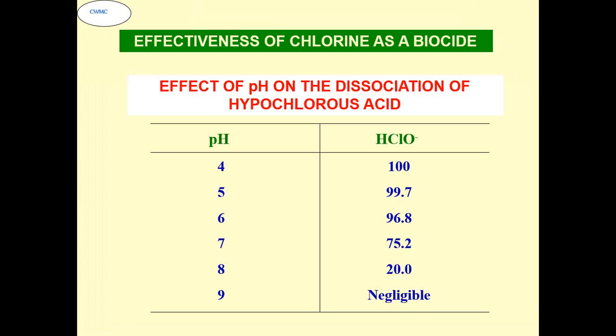See, chlorine is the most common biological control chemical used there. The problem is that beyond 8 pH, the effectiveness of chlorine is less than 20%. So it is dropping out at that level. So we need to see what we are dosing. It needs to be supplemented if your pH is higher.